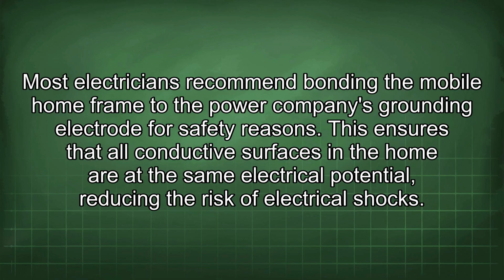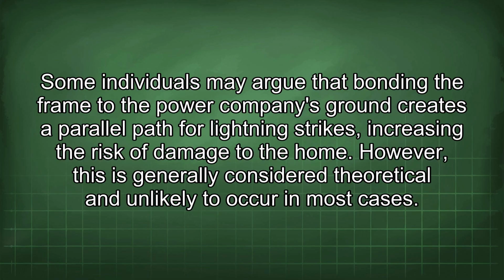This ensures that all conductive surfaces in the home are at the same electrical potential, reducing the risk of electrical shocks. Some individuals may argue that bonding the frame to the power company's ground creates a parallel path for lightning strikes, increasing the risk of damage to the home. However, this is generally considered theoretical and unlikely to occur in most cases.